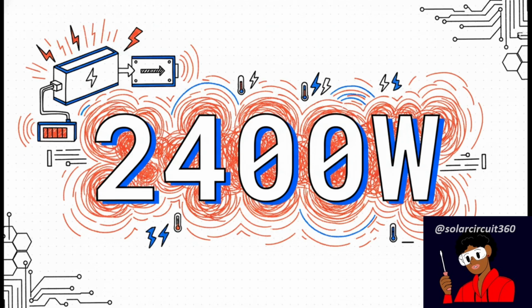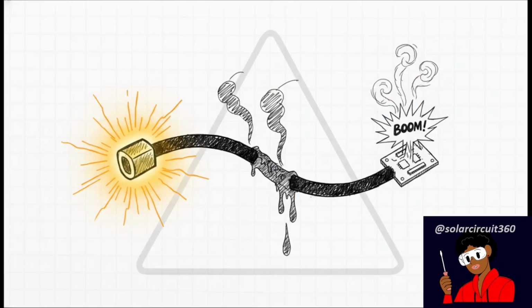Let's put that into perspective. If you've got a 48-volt battery pushing 50 amps to an inverter, it is churning out 2,400 watts of real, physical power. That is a lot of energy moving through your system, and naturally, all that energy generates heat. Because of that heat, your programmed discharge current absolutely cannot exceed the physical limits of your components.